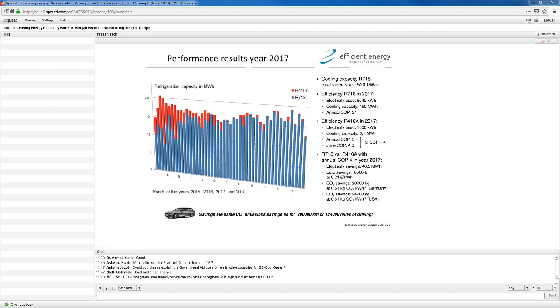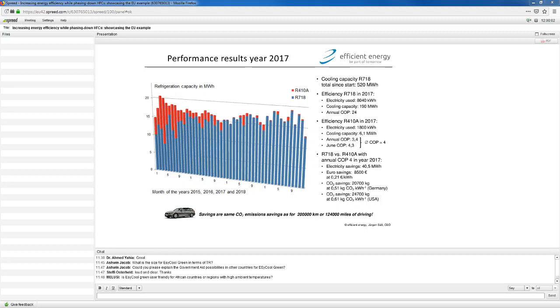What you can see here is in the beginning in 2014—this is the years 2015, 16, 17, and 18—they had a redundant system which was a R410A system, the red one, and then R718 is the number for water as a refrigerant. They had the water system as well, and then a normal redundant system, that means both refrigeration systems were big enough to supply or to fulfill the task and supply the full cooling capacity. The first month they ran both systems as you normally run redundant systems, so that means you want to get them equally quickly old or at least used. Then from September, which is indicated by the first nine on the bottom axis, then we said, well, you can just give us more capacity and then you will save more money.